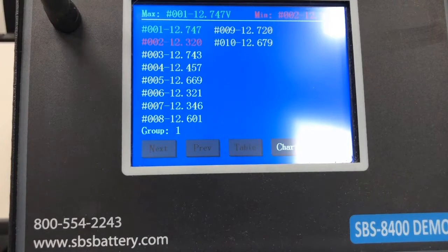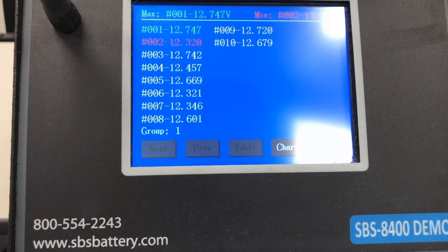Once all the wireless modules are connected and we're ready to begin the capacity test, you'll see that the colors on the displays are green, red, and yellow. The green values indicate the highest values. The red values indicate the lowest value at that point in time, and everything in between the high and the low will be in yellow. Over the course of the test, these colors will change with respect to what the conditions of the batteries are during the discharge.